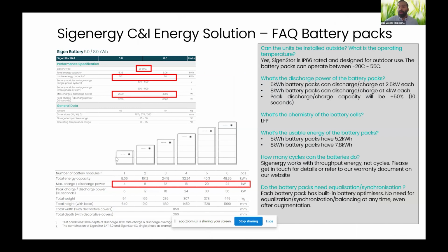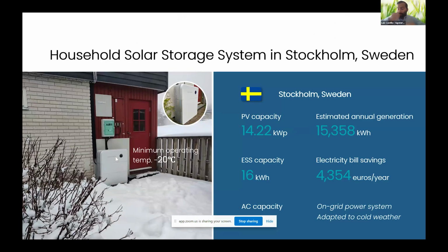Operation temperature of the system is -20 to 55 degrees. This is important, because when you install a system outside, fine, it could be IP65, it could be IP66, but that will not protect you from cold temperatures. If the battery cells inside the battery pack reach 0 degrees, they won't be able to charge and discharge. This is not just Sigenergy battery cells, these are all battery cells.